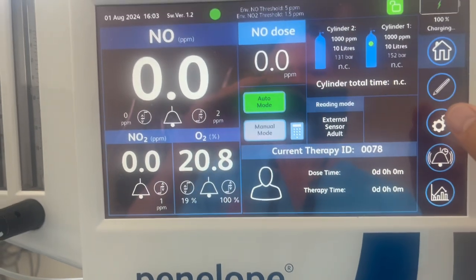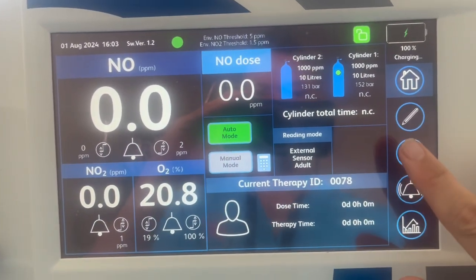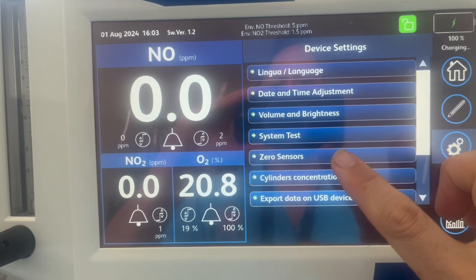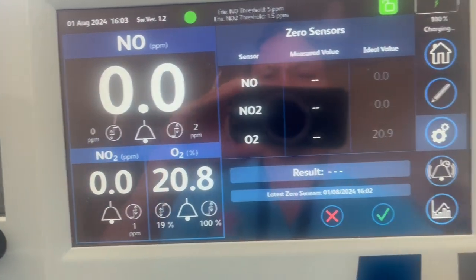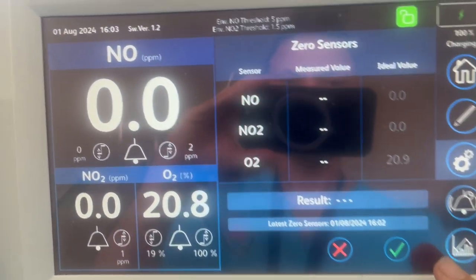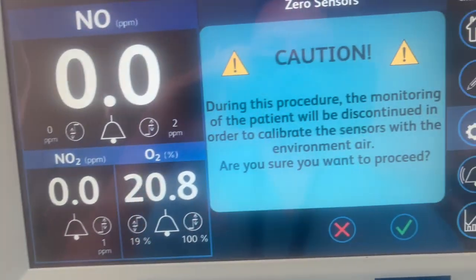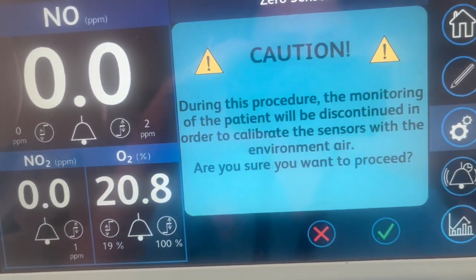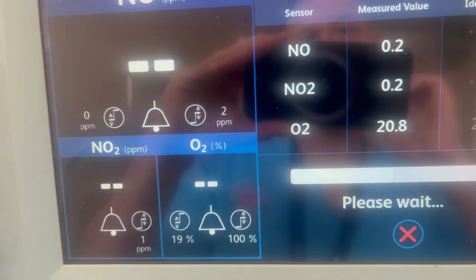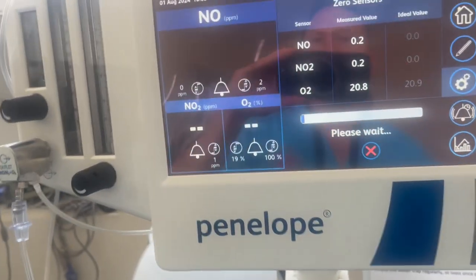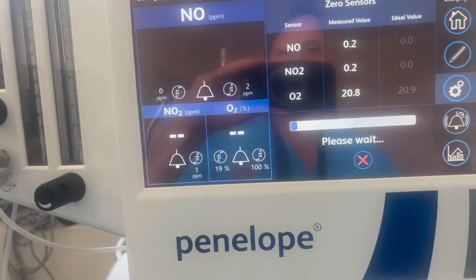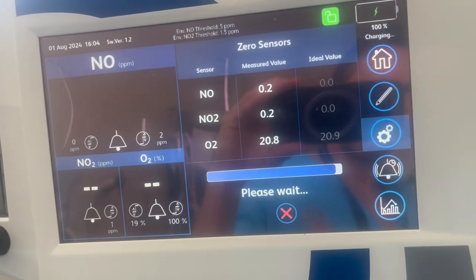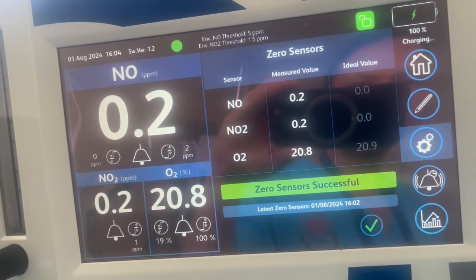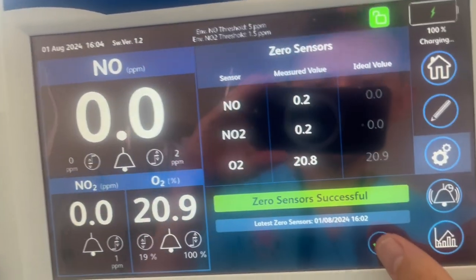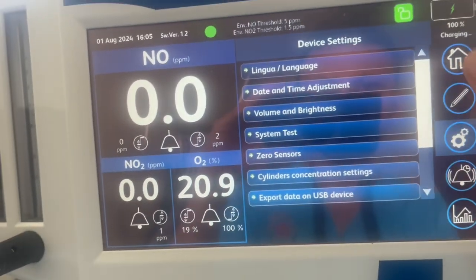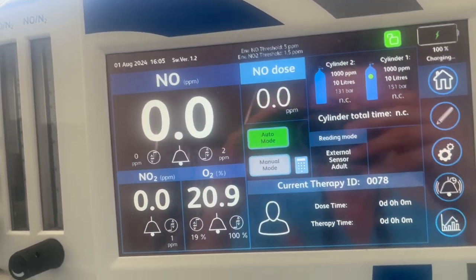You will have to perform a zero calibration on the sensors daily. Press settings, Zero Sensors and tick. During this period where the sensors are calibrated to environmental air, you won't be able to see what the sample line is reading, but the nitric will still be delivered at the set level. The only time this is not required is when the nitric therapy has just been commenced, as the machine does a zero calibration when it's switched on.